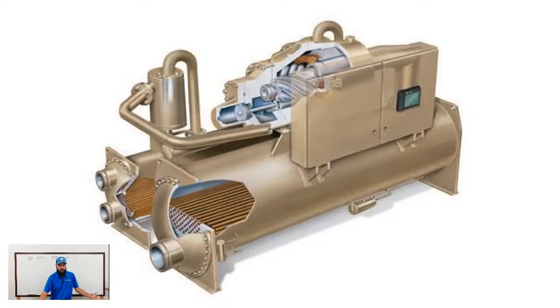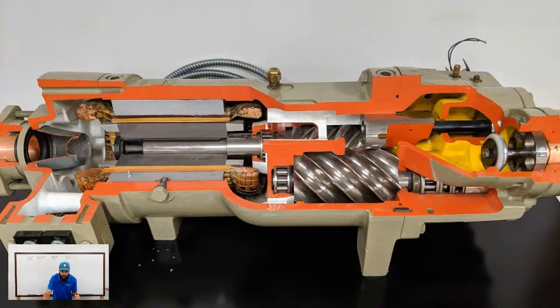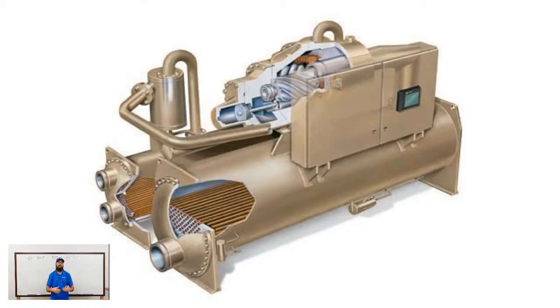Now, coming back to some of our pictures from yesterday, when we talk about a screw machine, if you look there in the middle of that compressor cutout, you'll see kind of a cylinder, a little disc shape thing. That is a representation of the slide valve, and that is what is controlling the load inside of that machine. So that slide, and I'll pull up one of these other breakdowns, you can almost see it better than the other one. Anyway, that slide is what is loading and unloading those screws.